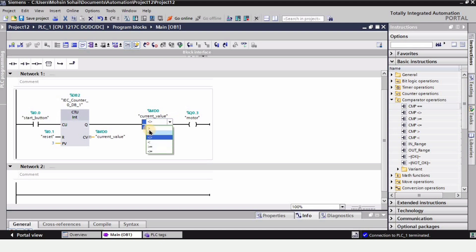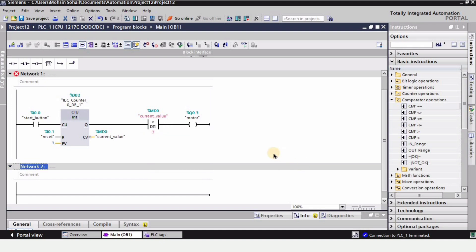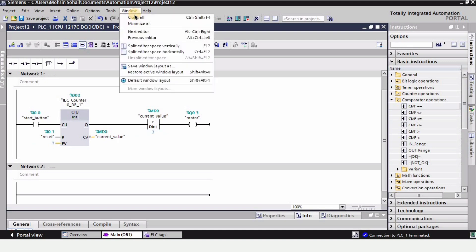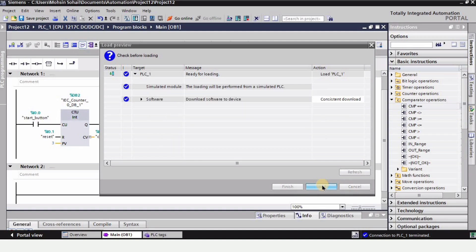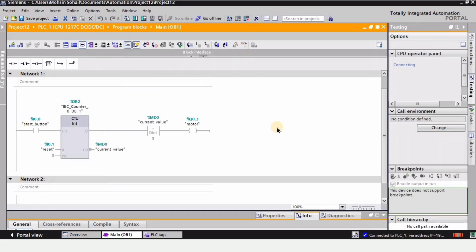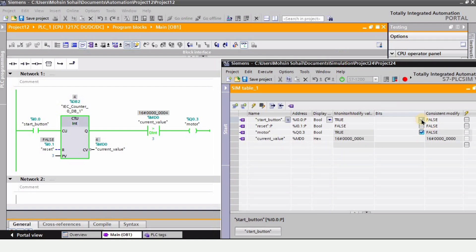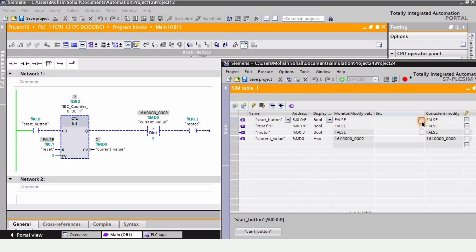Now I'm going to use the Greater Than instruction. Note that you can also change the data type here — we need to use double integer. I'll download the program and turn on monitoring mode to see how Greater Than works: when the counter value is greater than the comparator value, the output should turn on. After resetting the counter: one is not greater than three, two is not greater than three, three is not greater than three — the motor is still off. But on the fourth pulse, the motor turns on, satisfying the Greater Than instruction.